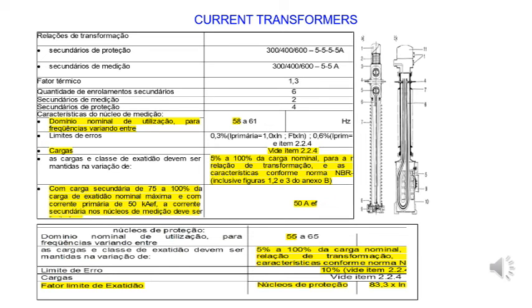There are some short-circuit tests in which you apply a short circuit in the primary side, and you measure the currents in the secondary winding to see if the ratio of currents is within certain margins which are specified for this test.